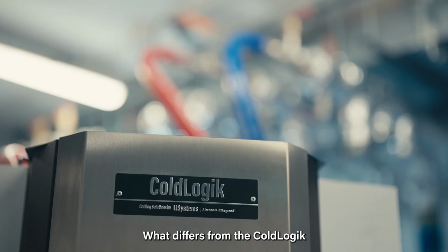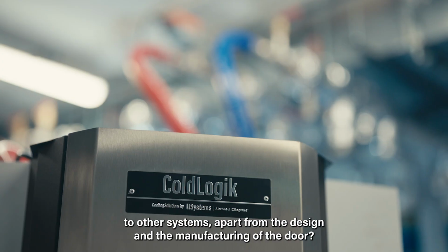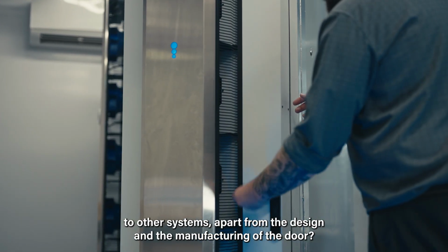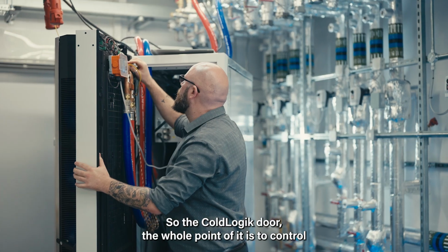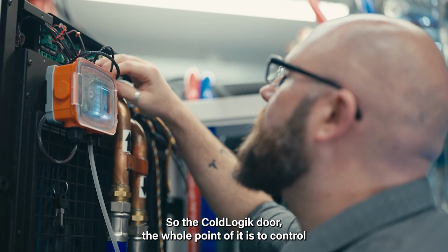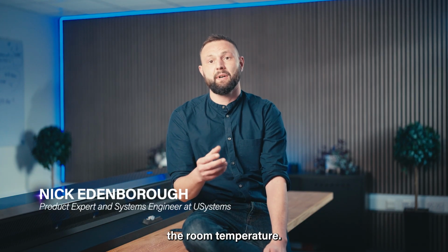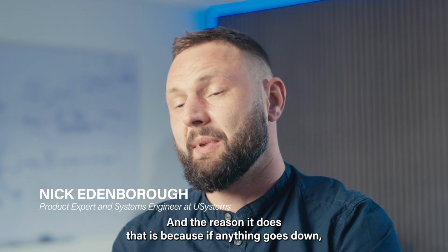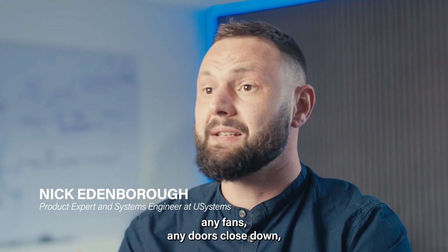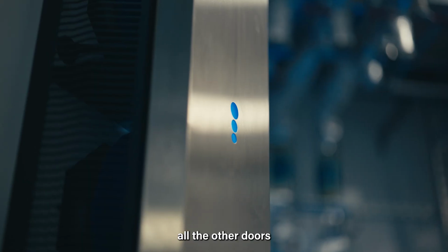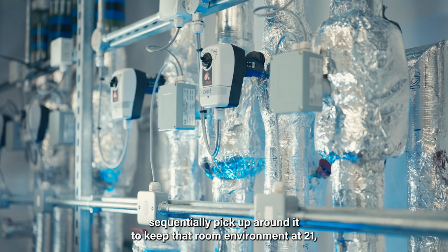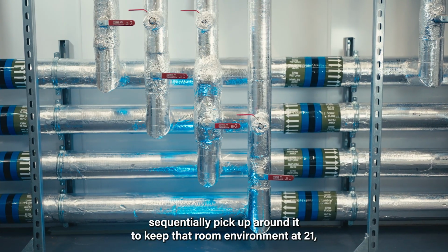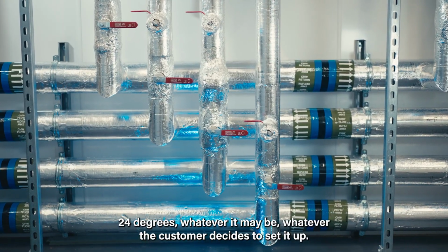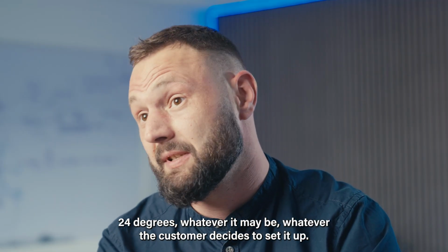What differs the ColdLogik from other systems, apart from the design and manufacturing of the door, is the way that it works. The whole point of the ColdLogik door is to control the room environment, i.e. the room temperature. If anything goes down, any fans, any doors go down, all the other doors then sequentially pick up around it to keep that room environment at 21, 24 degrees, whatever the customer decides to set it at.